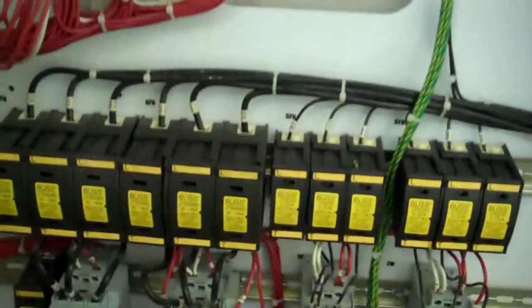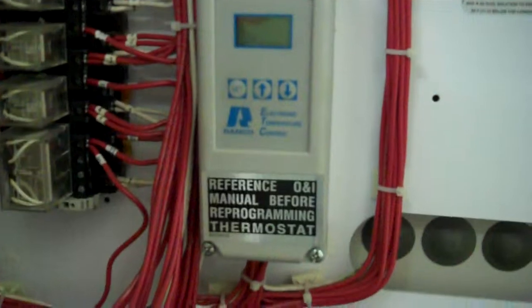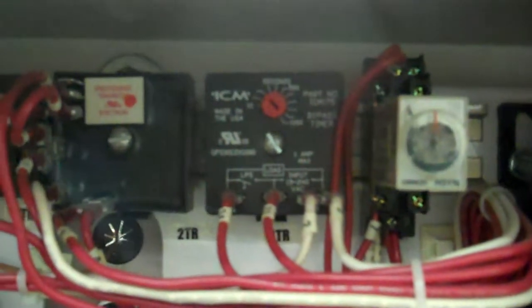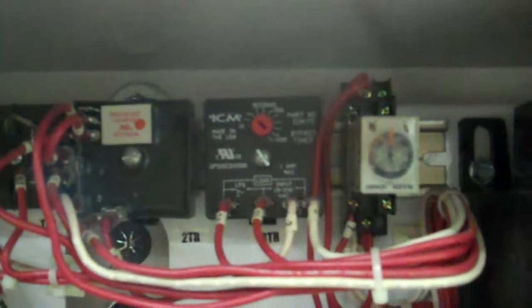Inside our control cabinet here, you have all the relays and contactors, overloads, controller transformer. This here is the high-low safety thermostat. That's preset. If it gets to a dangerously high or low temperature, it'll shut off. In here is some various timers, some related to the alarm, but this one here is important because that's the low ambient delay timer. So when this thing first starts up, it's not going to go off on any type of low pressure for the first minute or two until flow starts occurring and the system, I guess, warms up, if you will. Particularly ideal in a low ambient application.